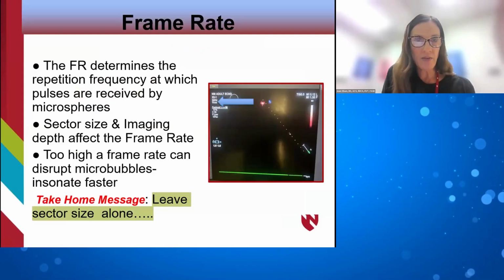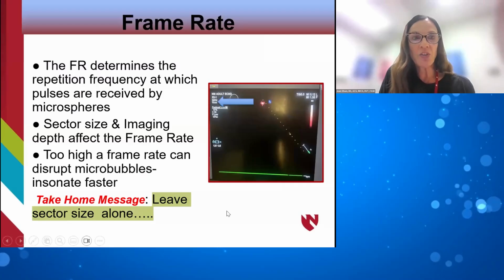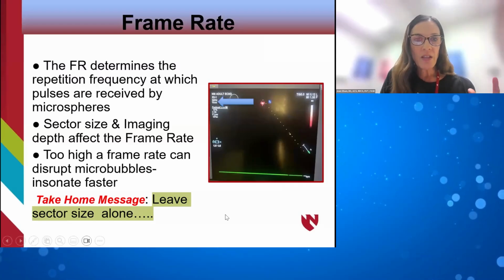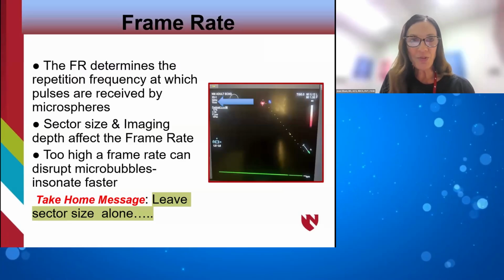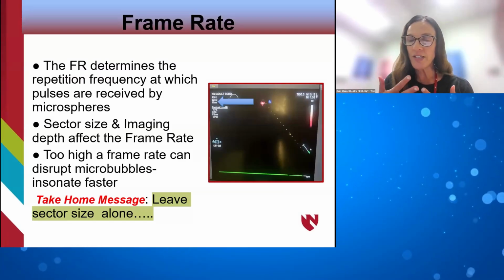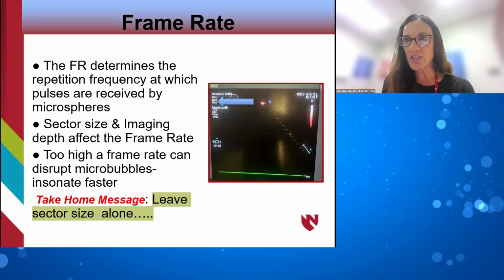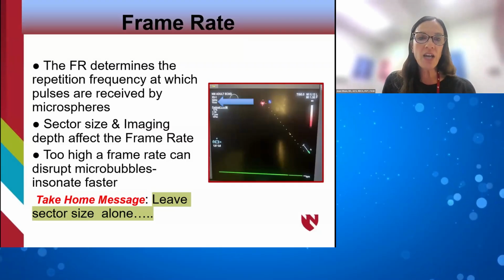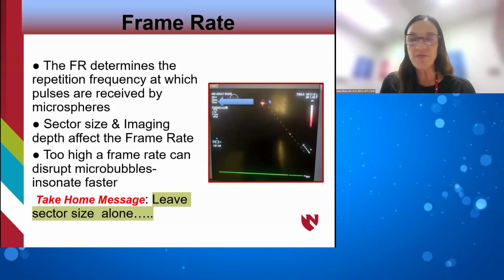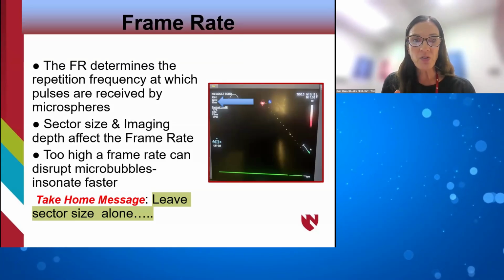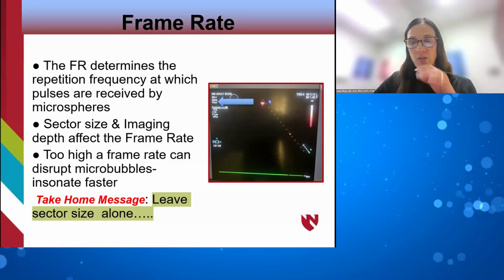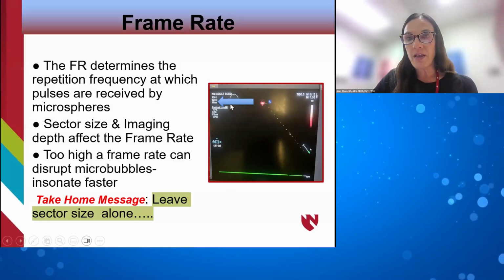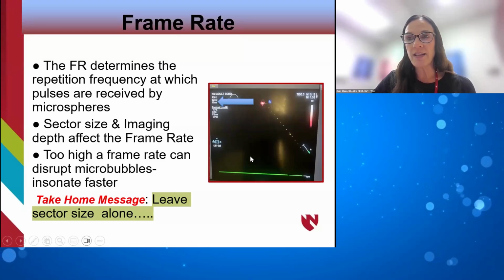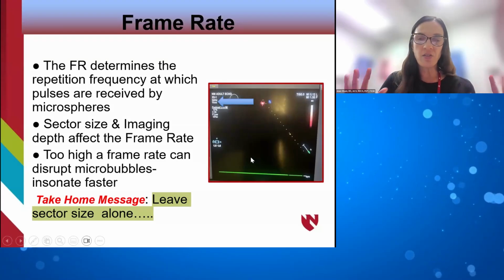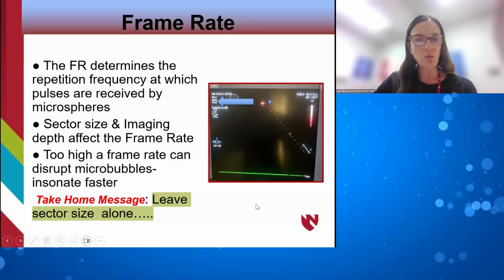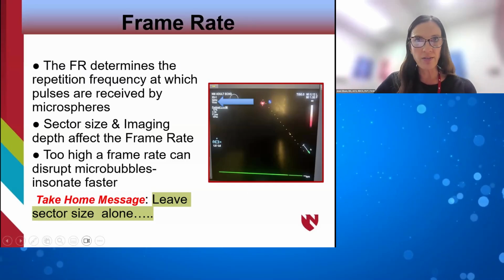Frame rate. The frame rate determines the repetition frequency at which pulses are received by the microspheres. Sector size and imaging depth affect the frame rate, which we all kind of know, especially with 2D imaging. You decrease your sector size, you're going to have a higher frame rate, and you're going to get better images most of the time. But too high of a frame rate can disrupt microbubbles and insonate faster. So the take-home message is that you leave the sector size alone for contrast imaging, especially this low MI technique, because the frequency can really affect that. It's kind of the opposite of your regular thinking, but leave that sector size alone. Once you start, that's where it stays, and you don't want to adjust it as you go along.